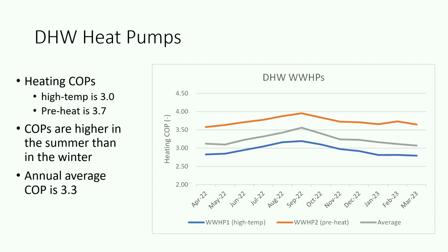The high temperature tank ran at a COP of about 3 overall across the year. The preheat tank ran at a COP of about 3.7. And of course, COPs, for all of them, go up in the summer because the loop is warmer. We expect that because it's a water-to-water heat pump. The overall annual average COP for this system, the combined COP of the two of them, was 3.3 on a gross or a plant COP basis.